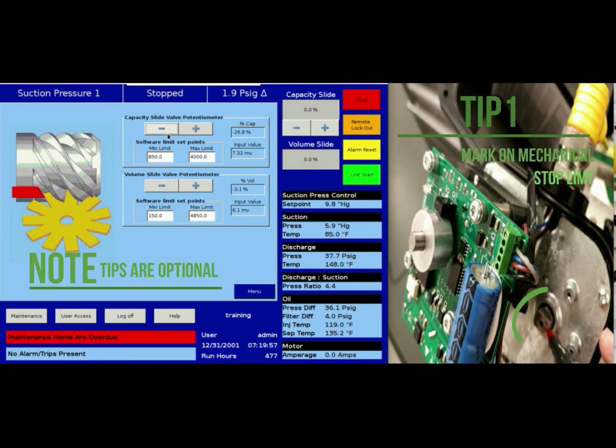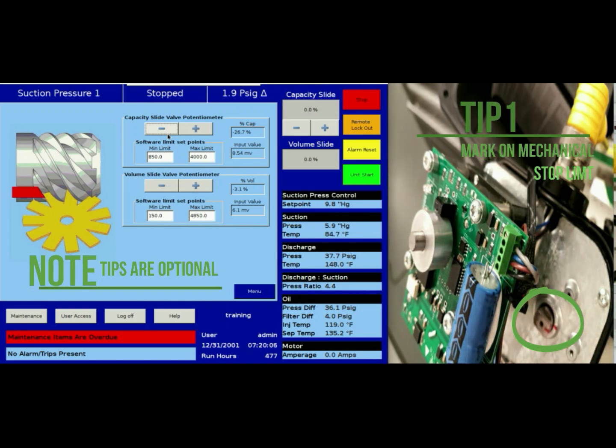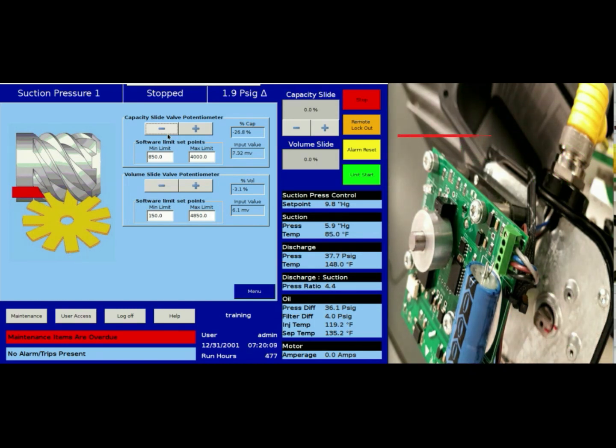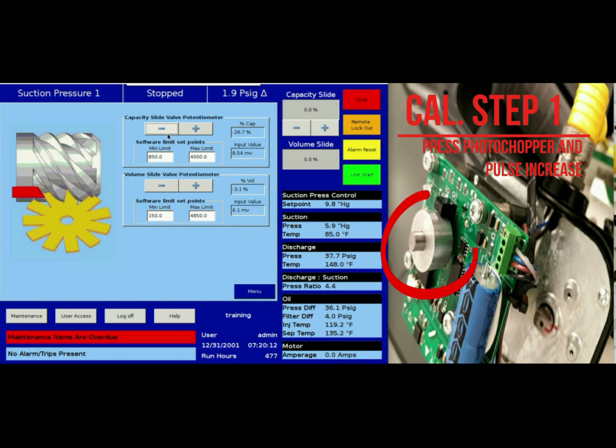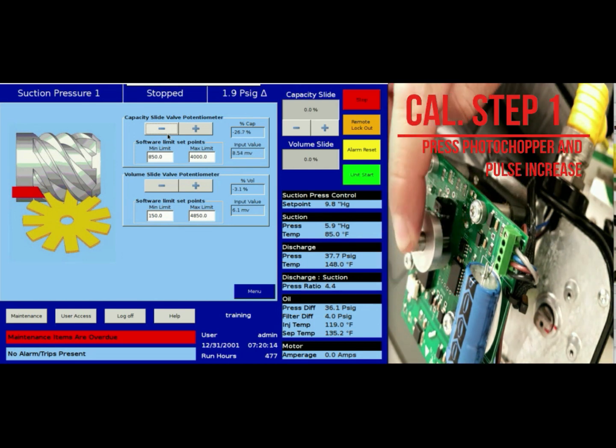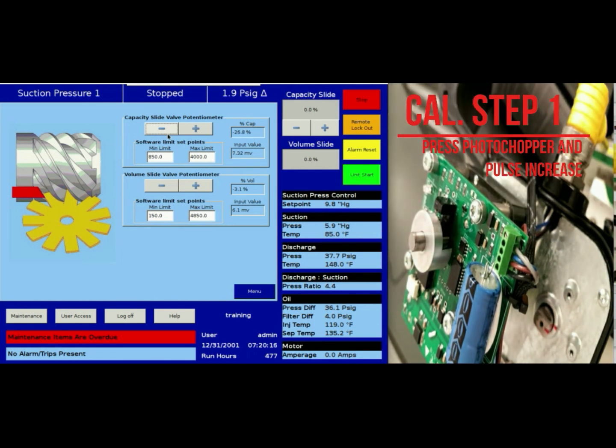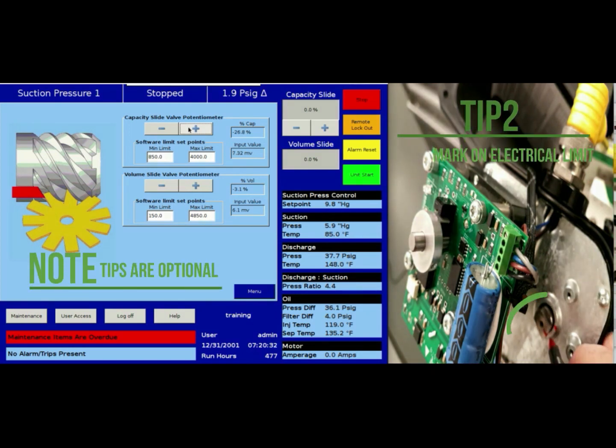Release the minus button. Next step after releasing the minus button is to release any tension built up at the photo chopper. To do so, push down on the photo chopper gently with your finger until the photo chopper has stopped to spin. After the tension has been removed from the photo chopper, we want to pulse the increase plus button momentarily. To do so, press and hold down on the plus button for 3 seconds, then release the increase button. This will allow some buffer between your mechanical stop and your 0% minimum value.